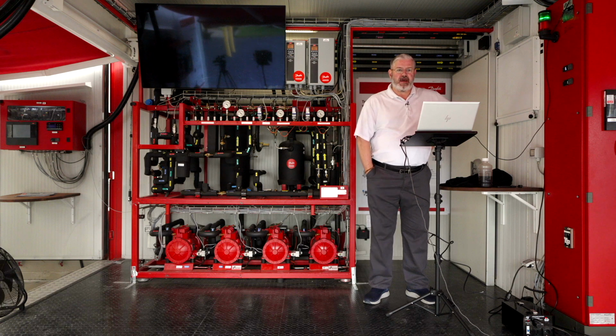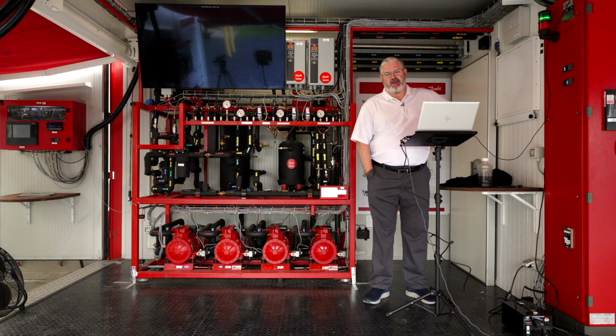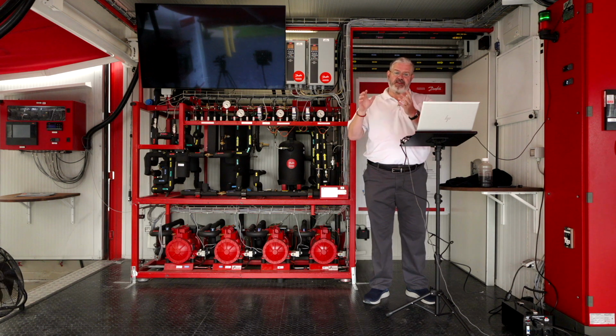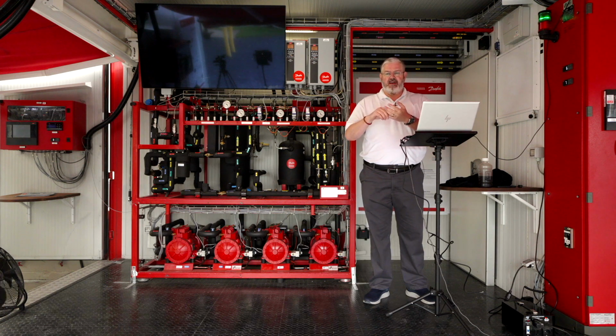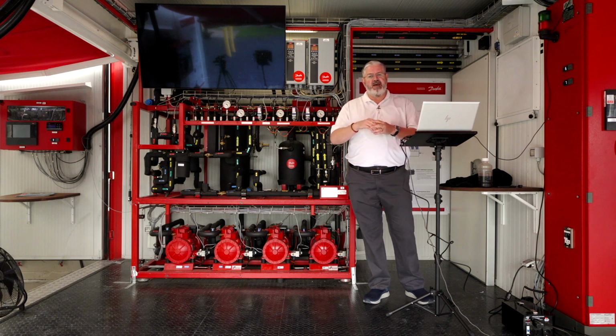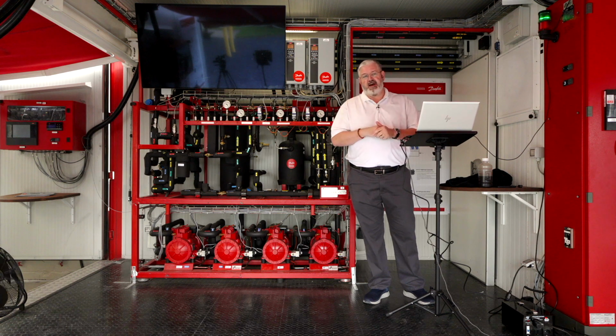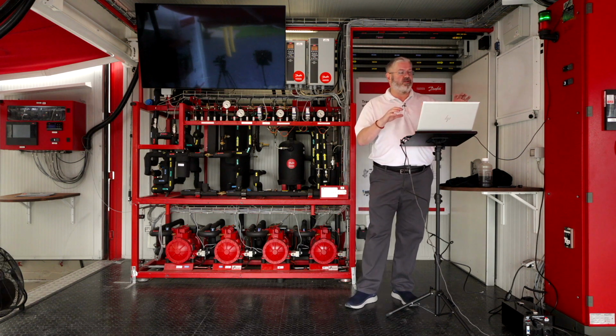So we have a question. Can this pack controller be used with a lower model Danfoss controller? If the question is in and around, do you need an 880? We have the 880 that kind of does everything, HVAC, lighting, energy. Then we have the 850, which I believe just gives you HVAC and refrigeration. And then the lower level, the answer is it will tie in and communicate with any of the models. Our base model is the refrigeration controller, so all the functionality is built into that. And then really what you're getting for the higher models is building control functionality and lighting control.